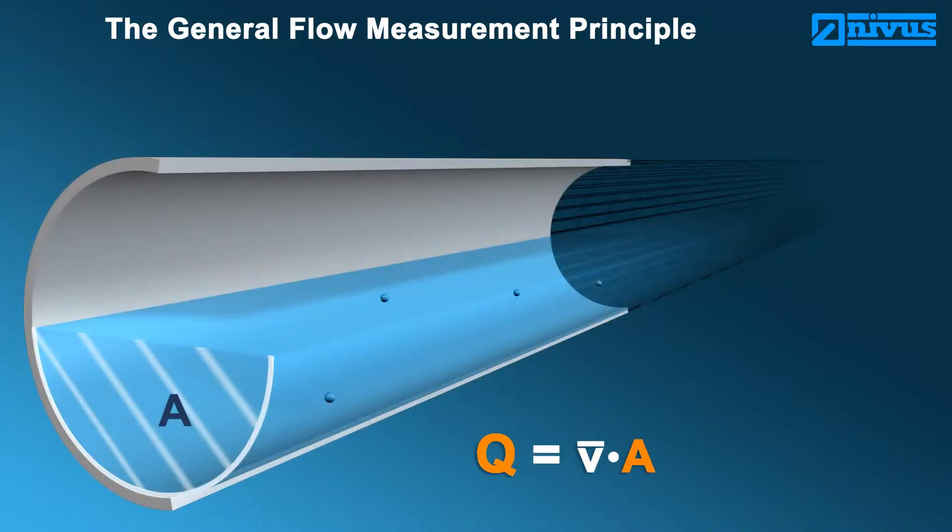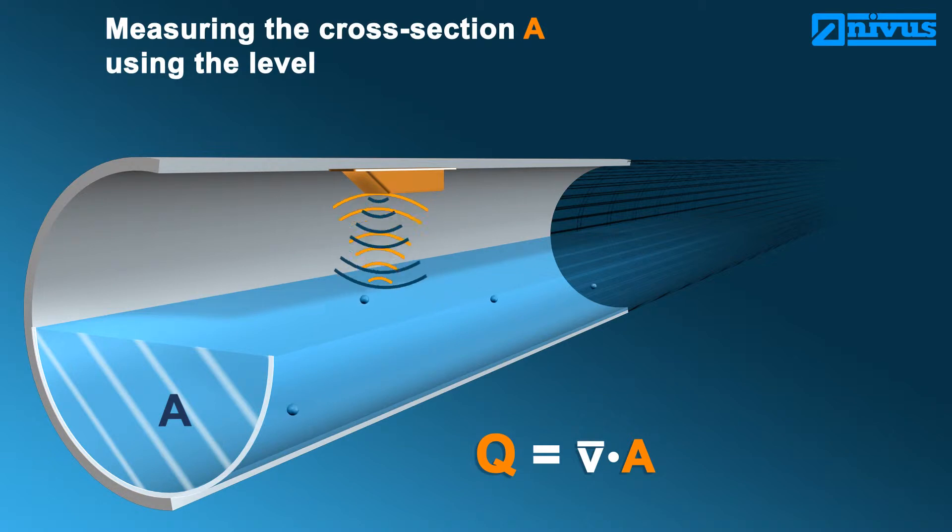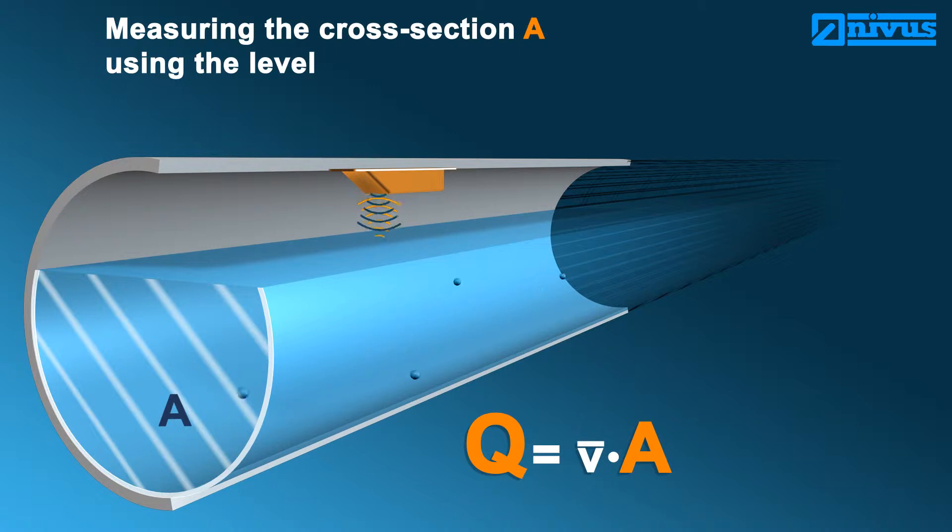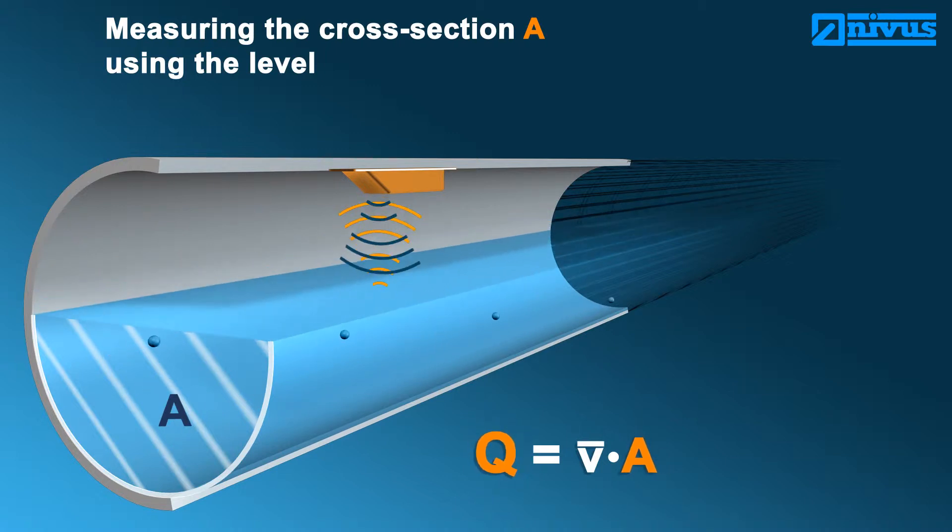How do we measure these factors? The flow cross-section A is determined by continuously measuring the level in consideration of the channel shape. If the level changes, the flow cross-section will change accordingly, and hence flow will change as well.